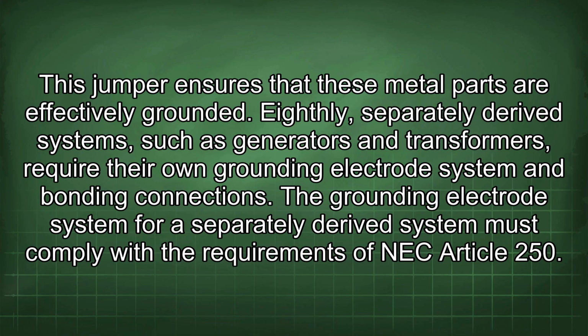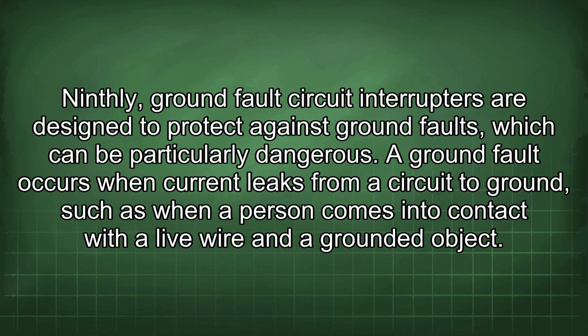Eighthly, separately derived systems, such as generators and transformers, require their own grounding electrode system and bonding connections. The grounding electrode system for a separately derived system must comply with the requirements of NEC Article 250. Ninthly, ground fault circuit interrupters are designed to protect against ground faults, which can be particularly dangerous. A ground fault occurs when current leaks from a circuit to ground, such as when a person comes into contact with a live wire and a grounded object.